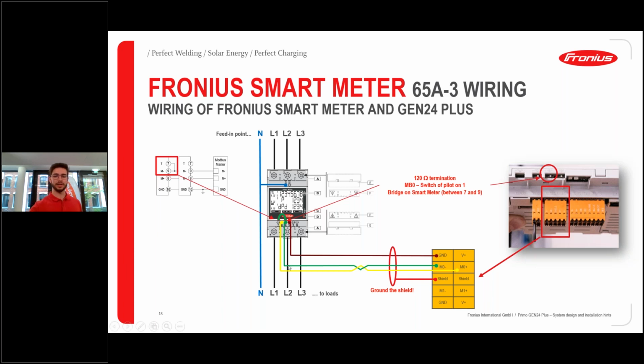And as we can see in our slide here, there is a possibility to ground the shield on the inverter itself. We have a direct connection here, which is called shield, and this is especially meant for that reason. So we can put the shield here on this position and ground it on one side. So that's the first two important ones. The third one is to have a twisted cable pair between data plus and data minus. In our case, it's the green and yellow cable, and we can see here in this schematic that they are twisted together. On the inverter, the connections are called M0, M minus and M plus. So this is just another wording for data plus and data minus.